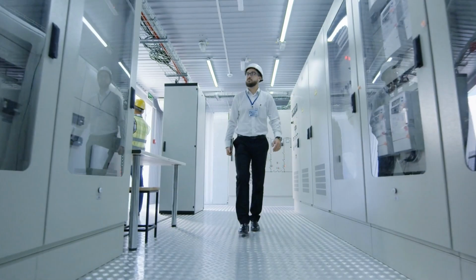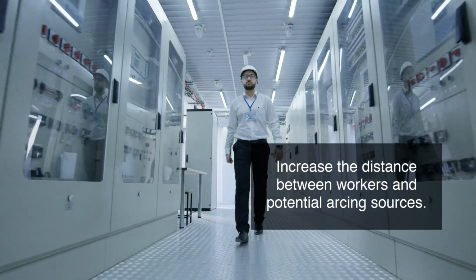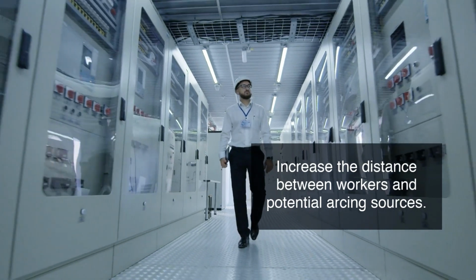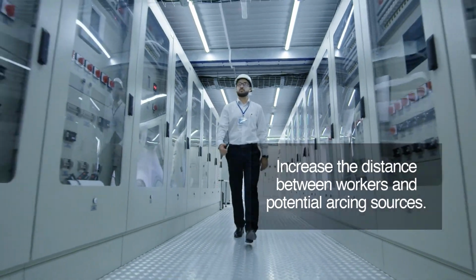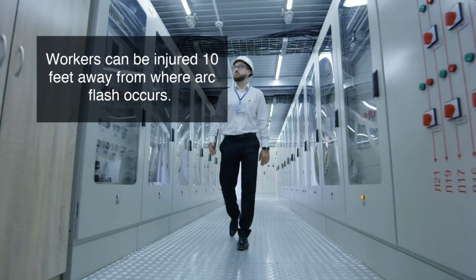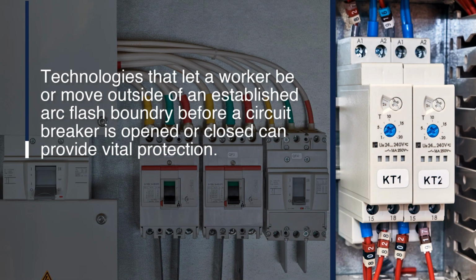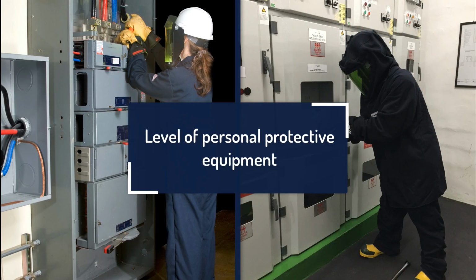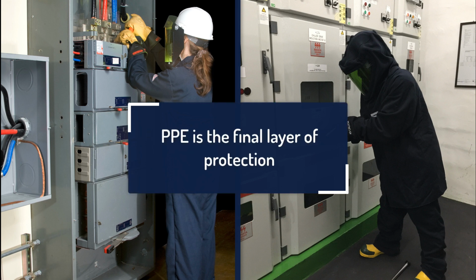One of the most important and effective ways to reduce arc flash hazards is to increase the distance between workers and potential arcing sources. Workers can be injured 10 feet away from where an arc flash occurs, and technologies that let a worker be or move outside of an established arc flash boundary before a circuit breaker is opened or closed can provide vital protection. In addition, an appropriate level of personal protective equipment provides a vital and always necessary layer of protection against injury or death in the event of an arc flash incident. PPE also is the final layer of protection.